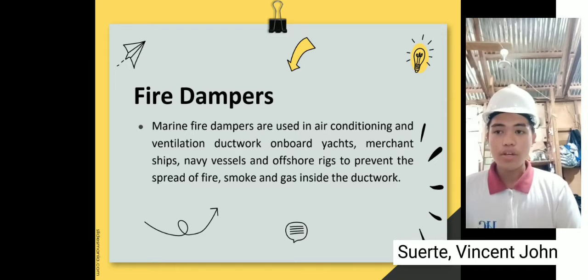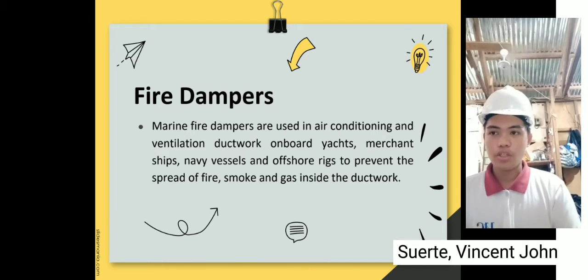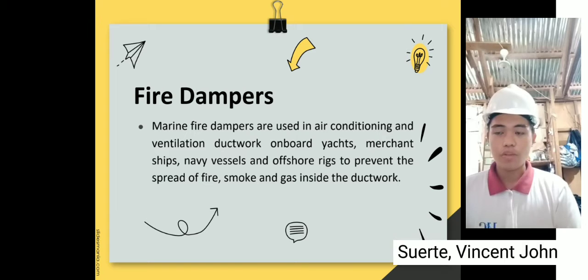This is considered one of the critical equipment on board. We know that fire dampers help to avoid the spreading of fire from one place to another. If the fire dampers fail to do their task, there is a high tendency of fire spreading without the crew inside the engine room knowing that they are at risk. So we need to use fire dampers because those are the possible consequences if marine fire dampers are not used in air conditioning and ventilation ductwork.